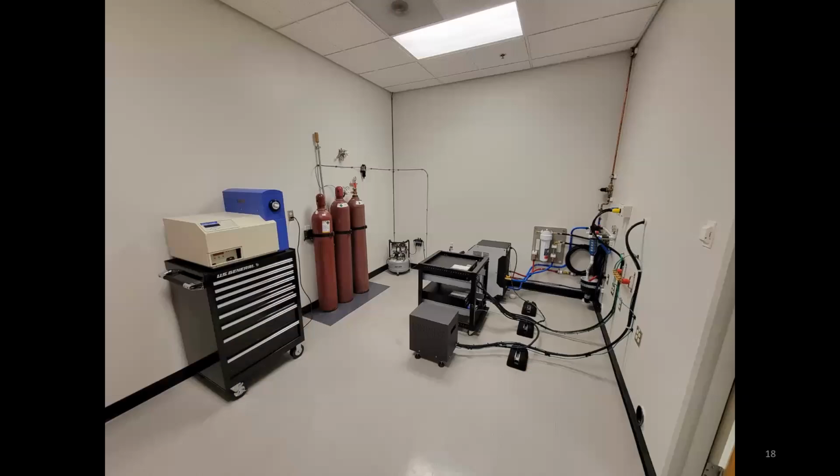So the room that we use, you saw the microscope room, we don't altogether get rid of having a support room with this microscope. It still needs some help. So this is a liquid chiller. So we send water through the microscope continuously to cool everything down, the optics, all the computer boards, all that kind of stuff's cooled. And I think some of the pumps are cooled as well, the little turbo pumps, liquid cooled. And then we have battery backup systems in case something should happen. And because it comes from Europe, we have to use a transformer to get the voltage just right.